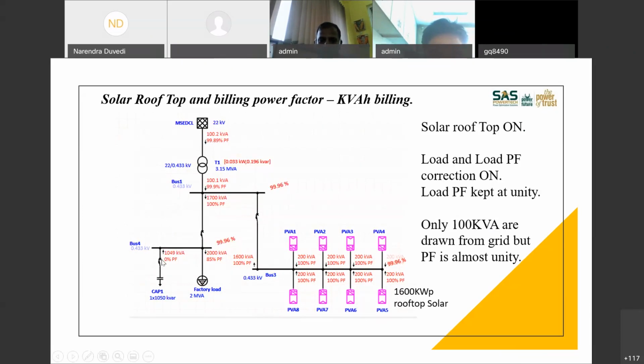In the third case, solar rooftop is on, load and load PF correction is on, and load PF is kept at unity. Only 100 kVA is drawn from the grid, but PF is almost unity. What is happening here is that, for the first time in this slide, I have now connected the solar and the load is also on. So I am drawing only 100 kVA from the grid, but my factory load is fully compensated. I mean, the load is still drawing 1700 kVA at almost unity power factor.